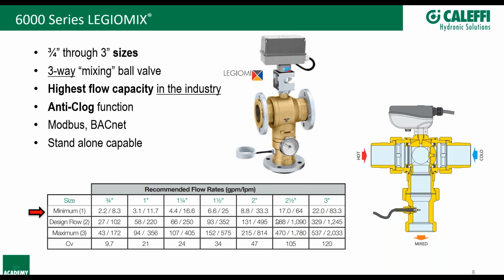That is a great question. I know there are some manufacturers on the market that have an over temperature solenoid function, where if it goes over a certain temperature for a certain duration, it'll shut off hot water flow to a building. That is something we're considering for the next generation of controls, but it's not something we have currently. We haven't run into a whole lot of issues with being knocked out of spec due to that, but it is a very valid question nonetheless. Like I said, there are no secondary safeties, but as long as the control is functioning properly, even if the tank is really high, it'll bring that temperature back down.